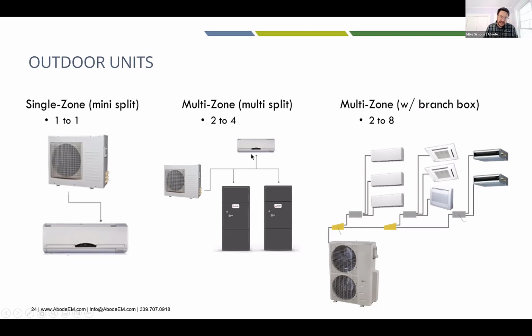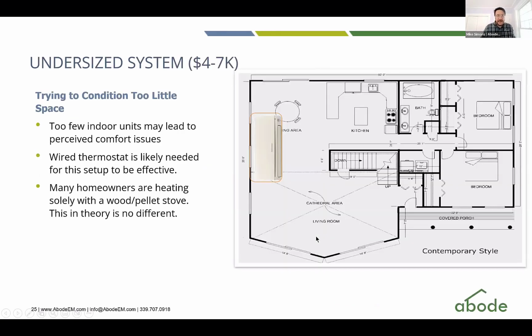And what would happen over here is you'd have a line set from this ductless mini split over to here, and then a line set for each of these ducted mini splits over to here. When you're dealing with like very big pieces of equipment, like 36,000 BTUs and greater, now, instead of it looking like one of these outdoor units, it looks like 2 of them stacked on top of each other. And these could be handling up to 8 indoor units. And instead of the lines all connecting back to the outdoor system, they would be connected to what's called a manifold or a branch box. And that equipment would typically be installed in the basement or the attic. So the indoor units run to the branch box, and then the branch box runs to the outdoor system, and it just kind of really cleans up the line sets. But they perform a little bit differently, and we'll talk about that a little bit more in training. But just know that with outdoor equipment, there's a lot of variability in them.